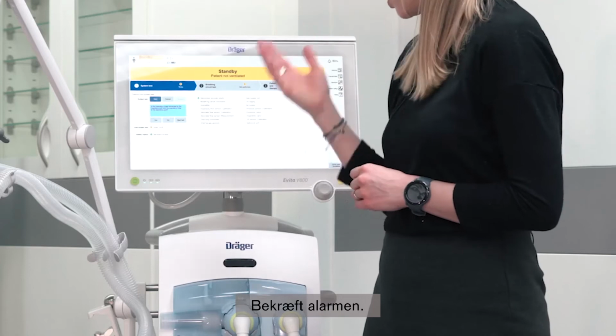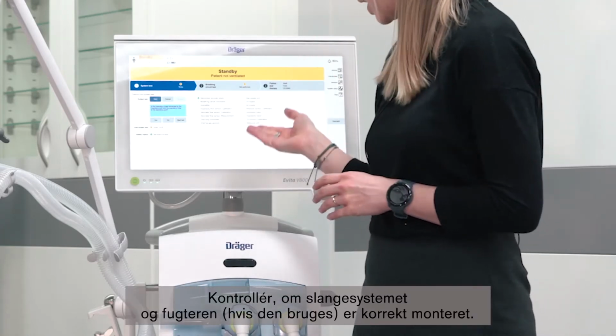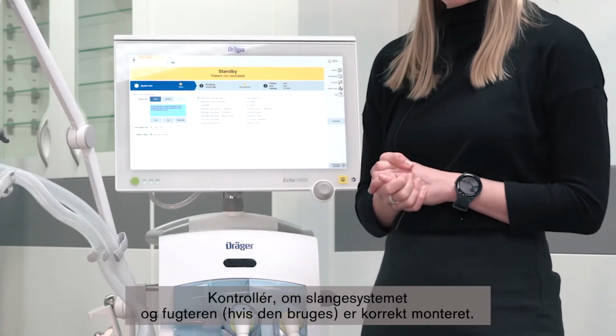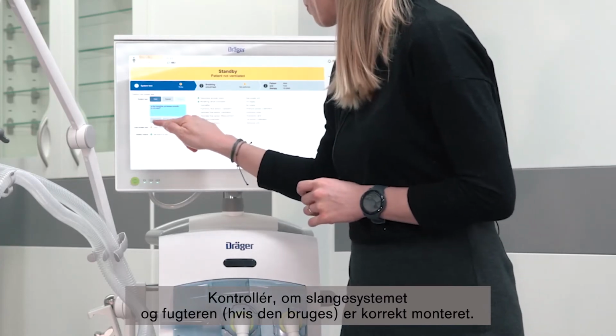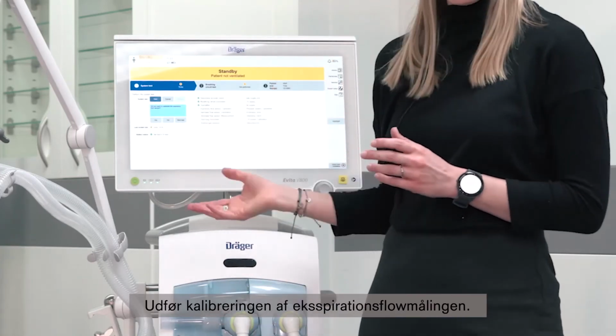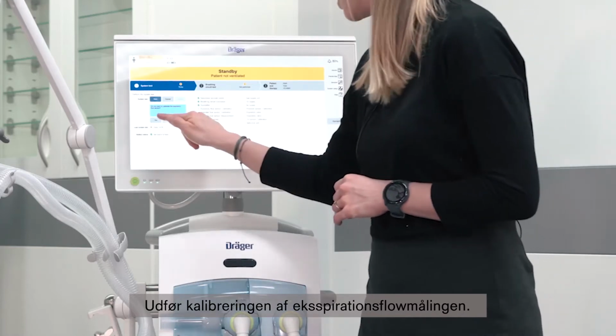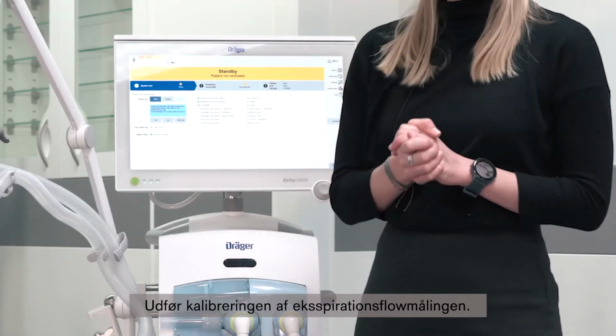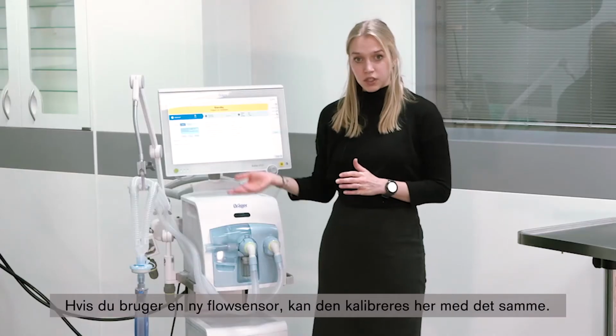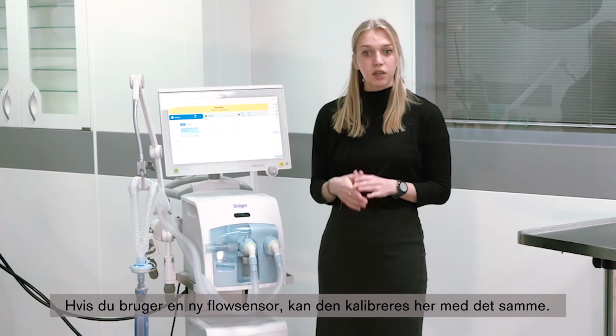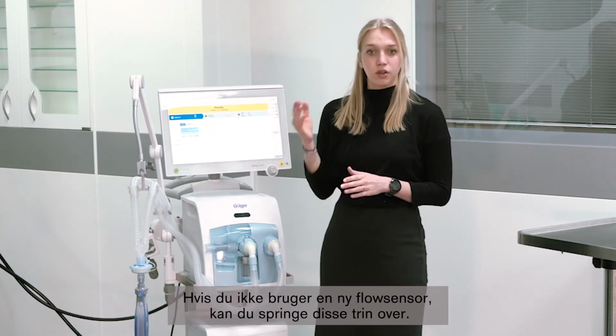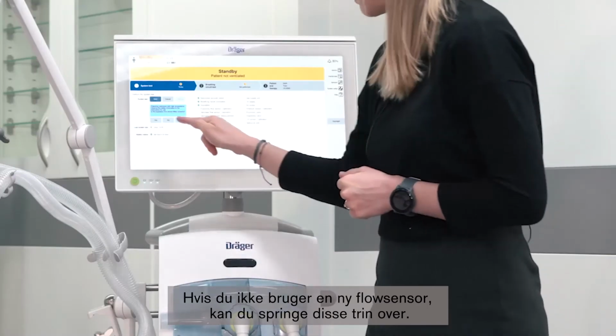Acknowledge the alarm, check whether the breathing circuit and the humidifier, if used, is correctly assembled. Perform the calibration of the expiratory flow measurement. If you use a neonatal flow sensor, you can directly calibrate that here. If you do not use a neonatal flow sensor, you can directly skip these test steps.